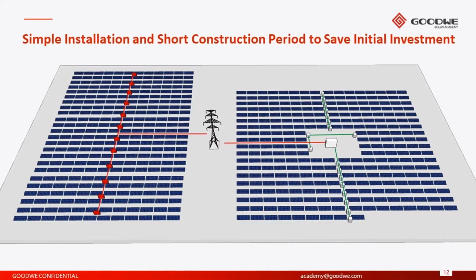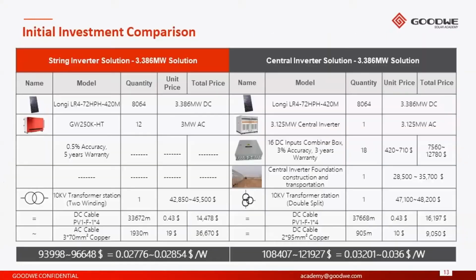One of the advantages at the moment is in terms of the initial investment comparison. I won't go into detail of what this table entails. However, at the end of the day, since the costs of string inverters have reduced rapidly over the last 5 years, the cost of a string inverter solution when compared to a central inverter solution, regardless of the size, whether it's a 3.386 megawatt solution, as you see on the screen here, or a 2.5 or a 1 megawatt solution, which is very popular at the moment for the Polish tenders.